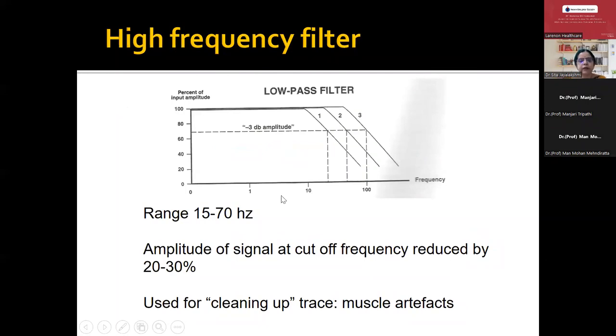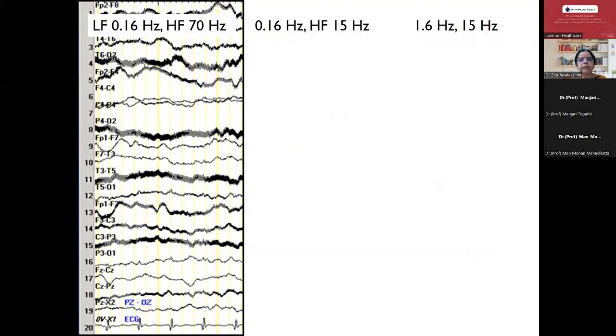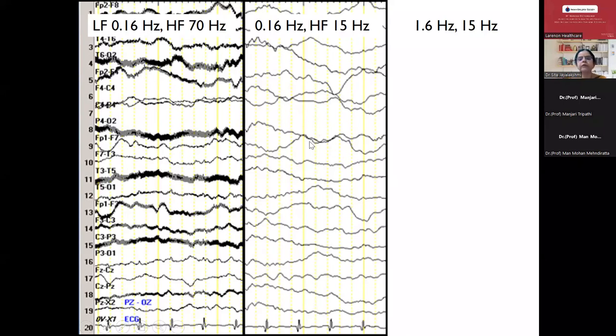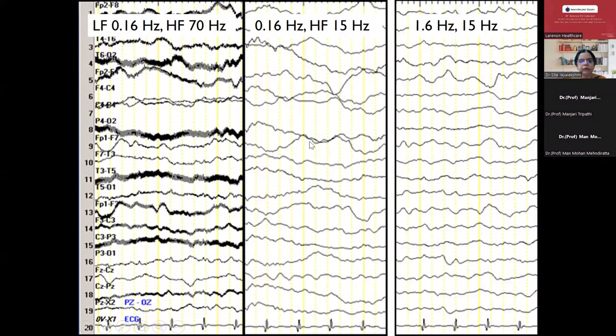The high frequency filter — usually we keep it around 70 hertz. Ideally, we should record at 70 hertz only, even if the EEG is not very smooth. It is the amplitude of the signal at the cut-off frequency which is reduced by 20 to 30%. Recording at 70 hertz may look noisy, but if you change it to 15 hertz to get a smooth recording — that's what most of the time we see in references from outside — you see a very smooth EEG which is not at all good. We should always record as far as possible at 70 hertz.